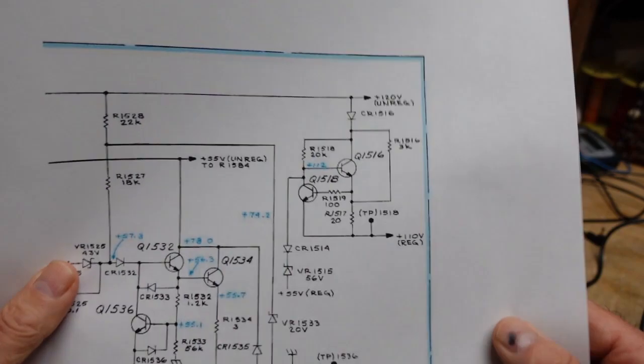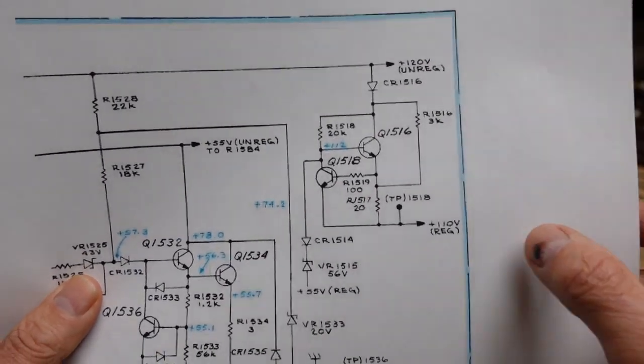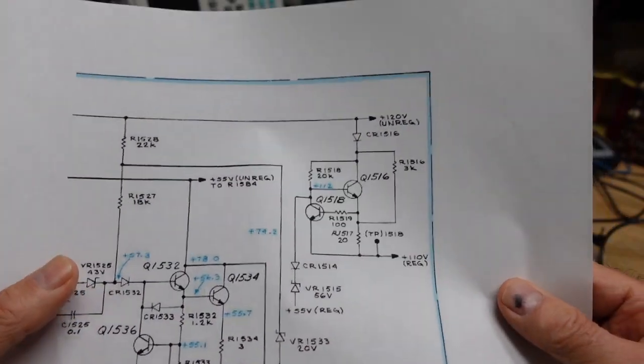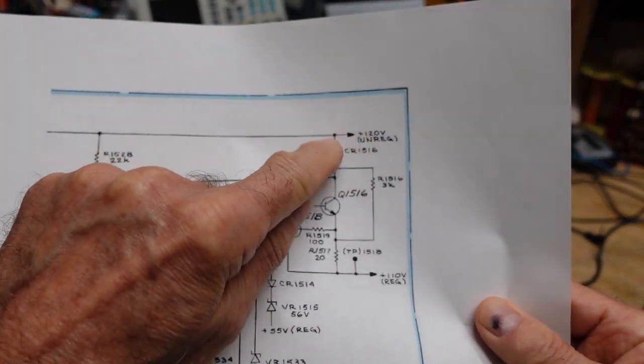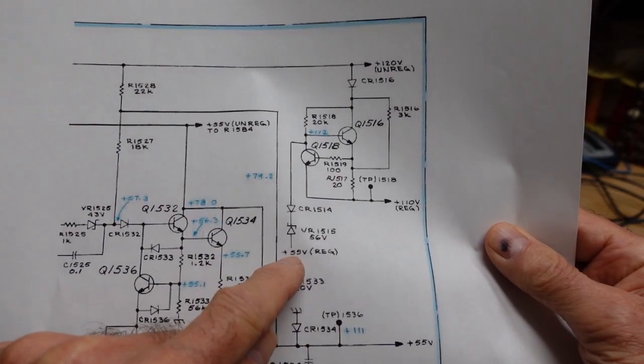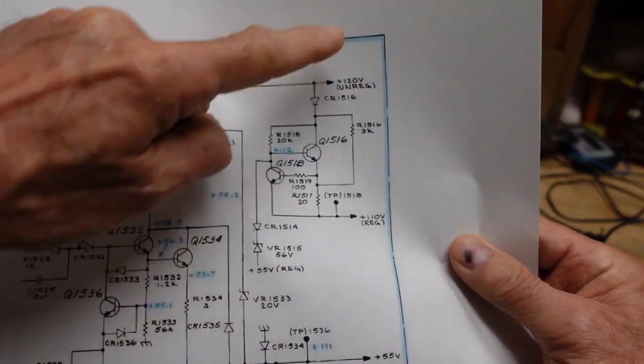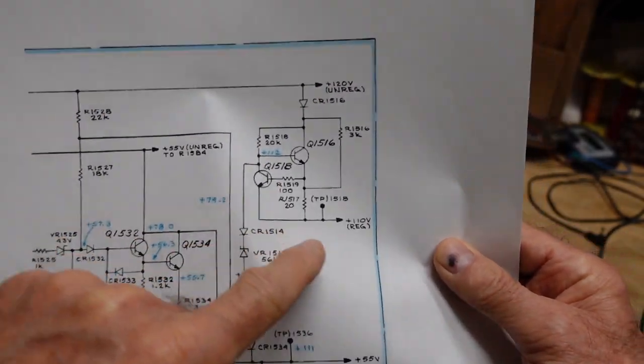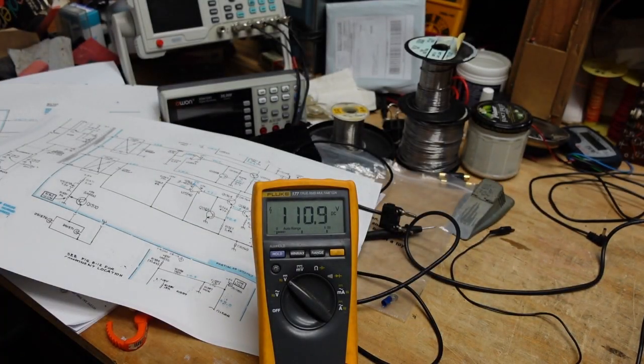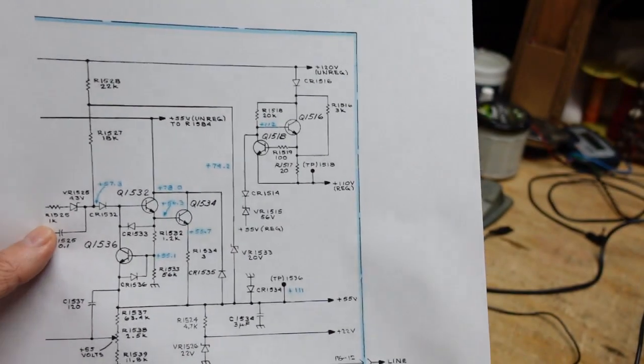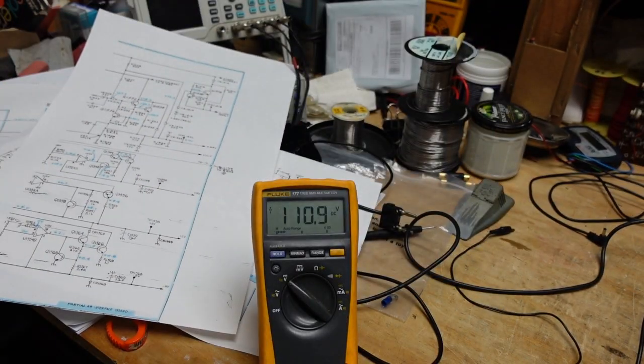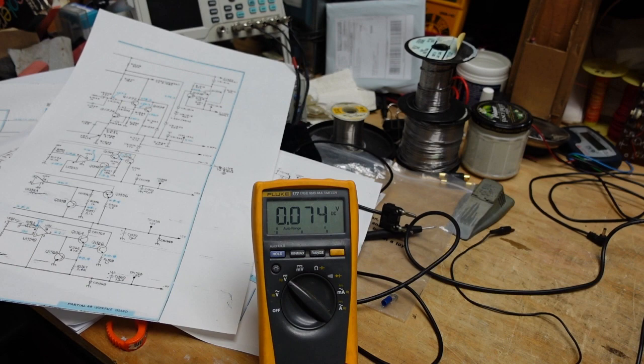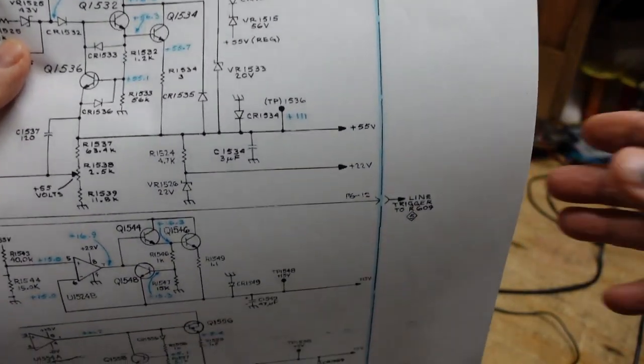So if we look right at the top here, we can see that if we have our 110 volt, that should indicate that our 120 is good and that also our positive 55 is good, because without those we don't get this. Now if you look at the meter, our 110 looks pretty good, so I'm going to go check the 55, which as I've said should be good. Let's see where that is, that looks like it's here. Our 55, as expected, is good.